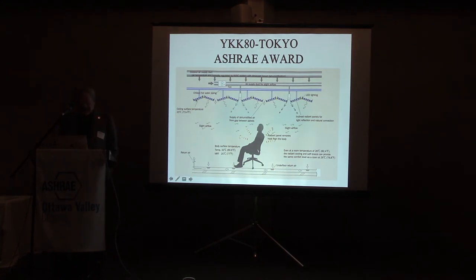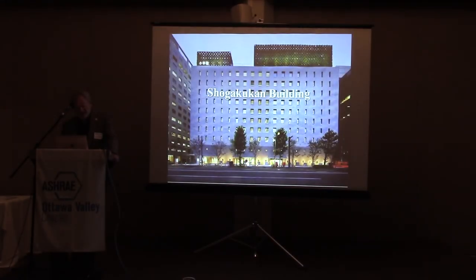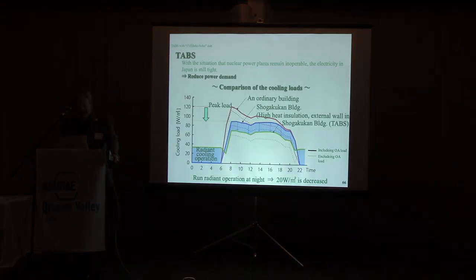So that's how they made their panels, and at the perimeter they also have chilled beams. They have also done measurements, and in the documentation for ASHRAE there are also measurements of the indoor environment. And last year they just opened the first building in Japan with the TABS system, where you have pipe integrated in the concrete slab. They calculated what the normal peak load would be, then what it would be with a good design, and how far they could bring the peak load down using a TABS system.